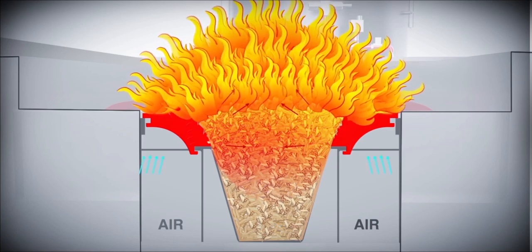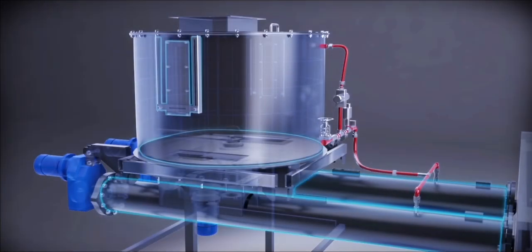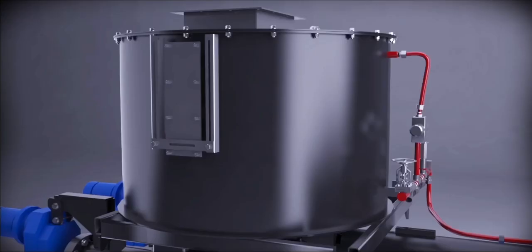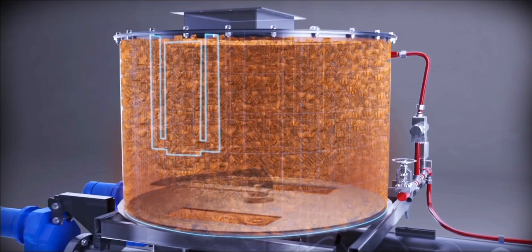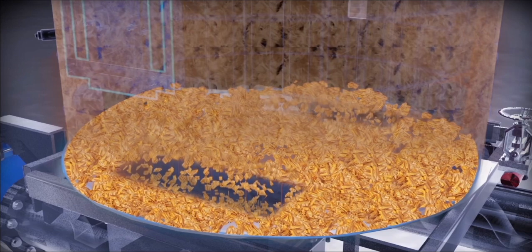The fuel feeding system in the UFS system consists of a rotary dosing bin and screw feeder. The rotary dosing bin offers small storage of fuel and helps avoid ingress of air from the fuel feeding side. The rotating arm inside the dosing bin helps in distribution of fuel and eliminates fuel bridging. The screw feeder pushes the fuel inside the retort of the Underfeed Stoker.